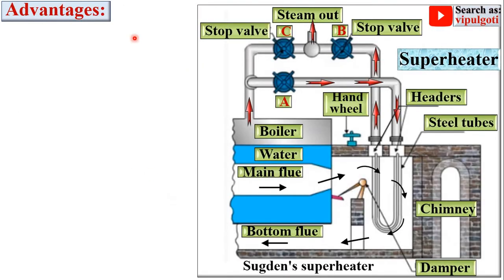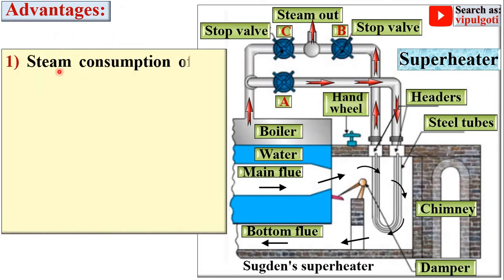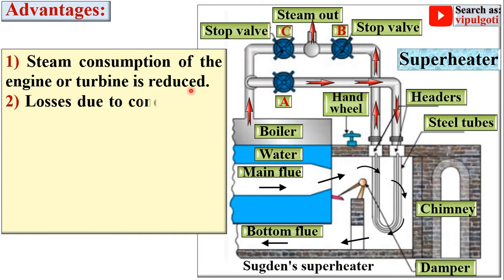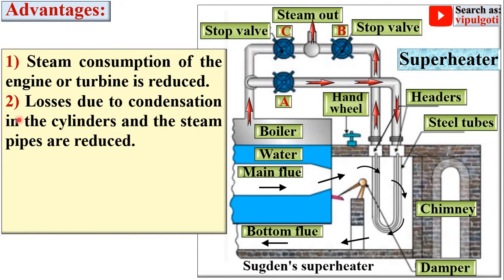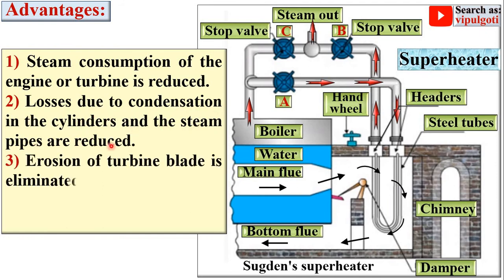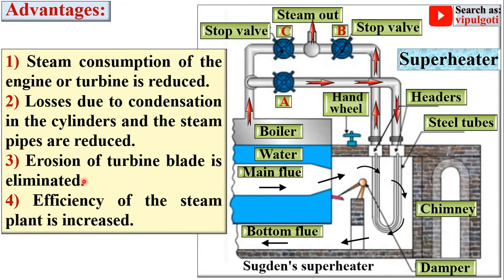Now, advantages of the superheater. Steam consumption of the engine or turbine is reduced. Losses due to condensation in the cylinder and steam pipes are reduced. Erosion of turbine blades is eliminated because there are no water particles in the steam. The efficiency of the steam plant is increased.